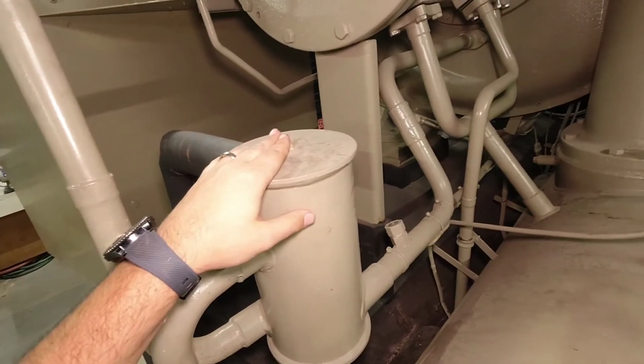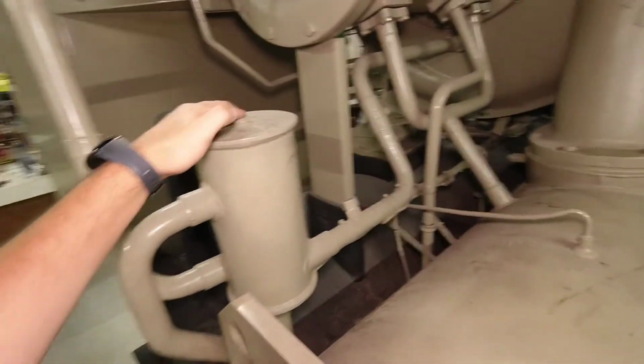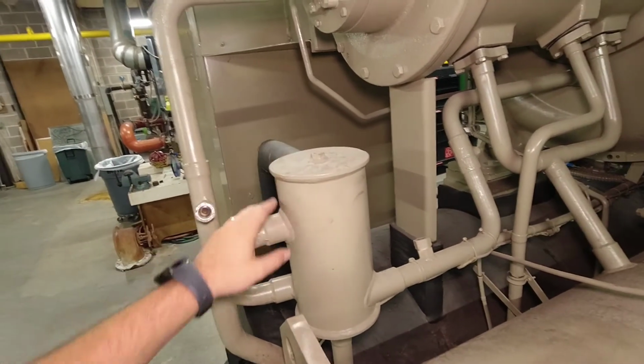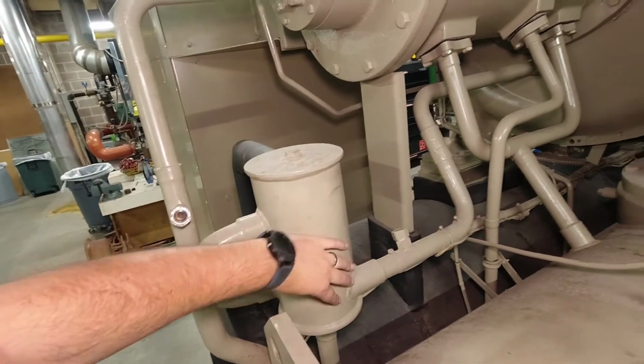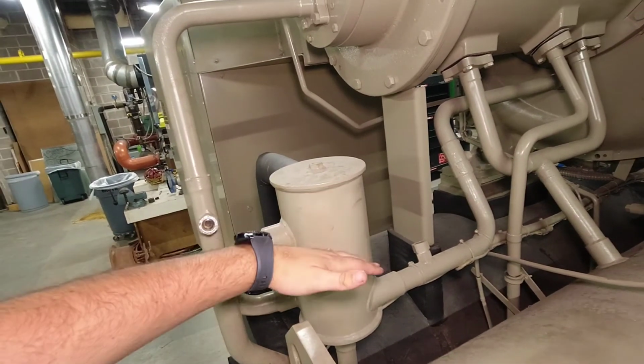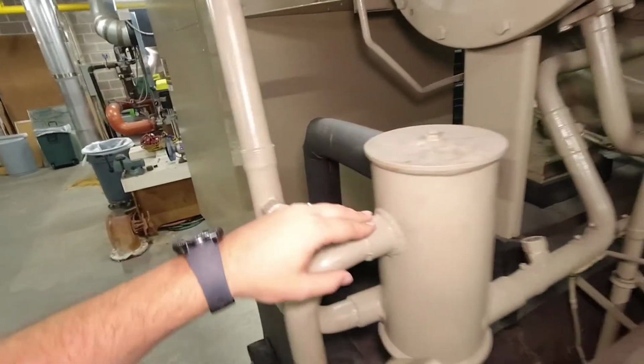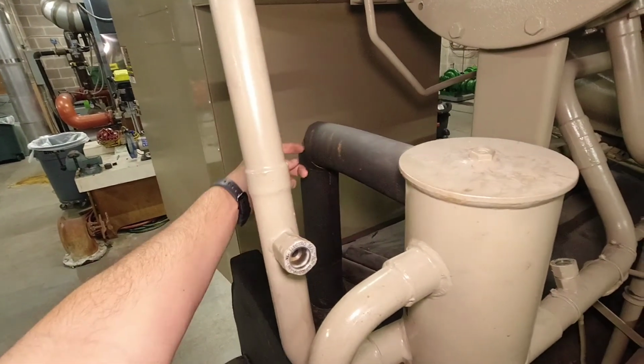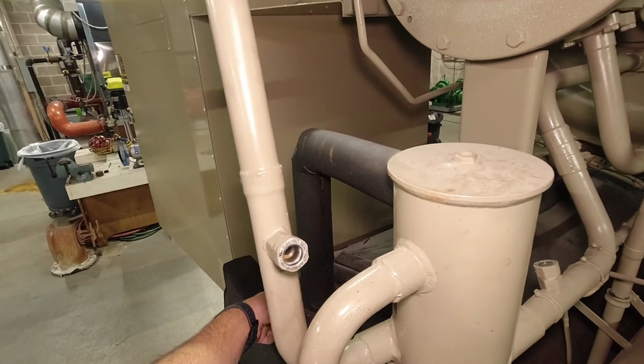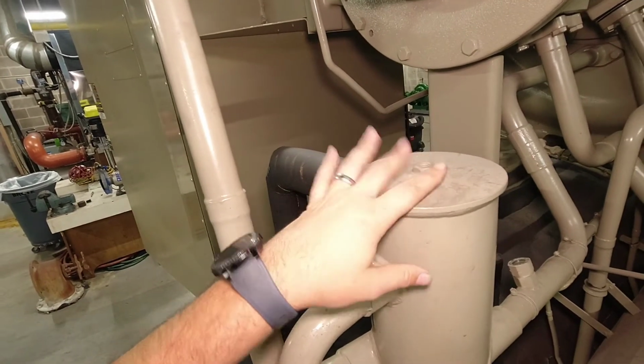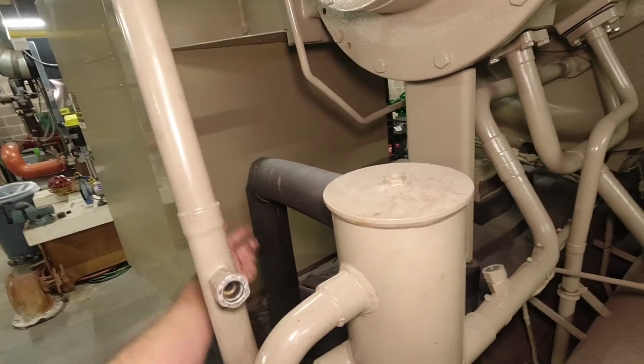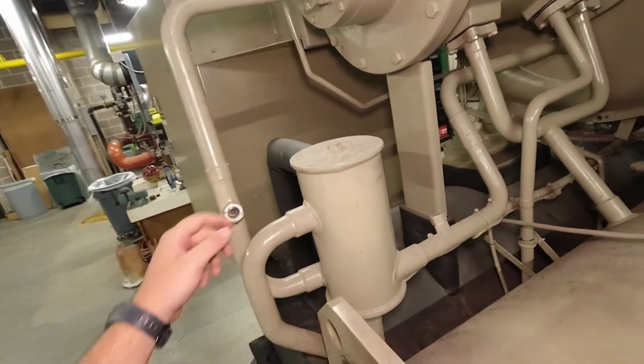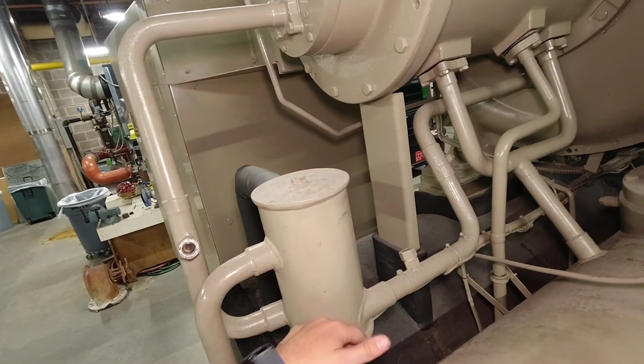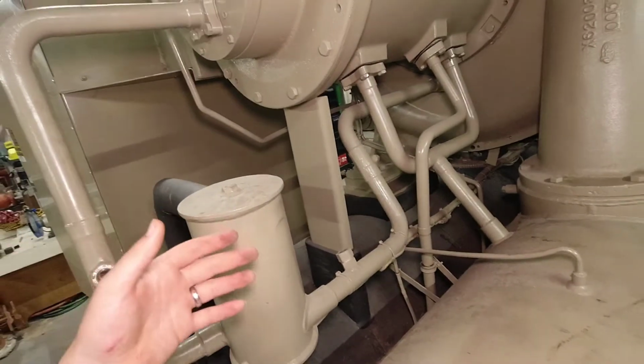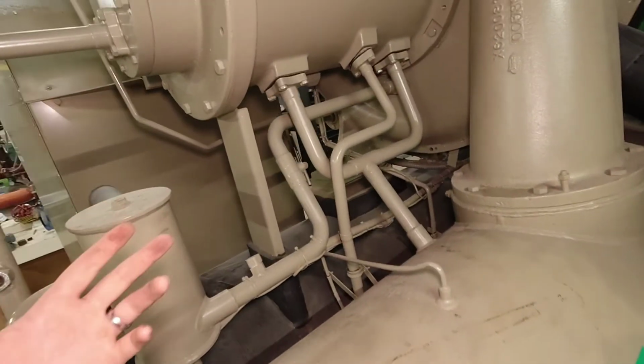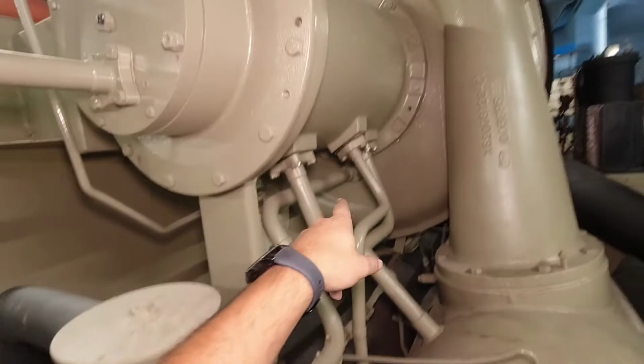This is the oil return line coming off of the motor bearing, and it's going to drain down into this little tank assembly, and this is an oil refrigerant separator. The goal of this is that the oil will collect in the bottom of this reservoir, and the refrigerant will rise to the top. Any gas or refrigerant that flashes out of the oil can then pull back into the evaporator, so it doesn't get into the oil and collect and build up and create problems because of refrigerant in the oil.